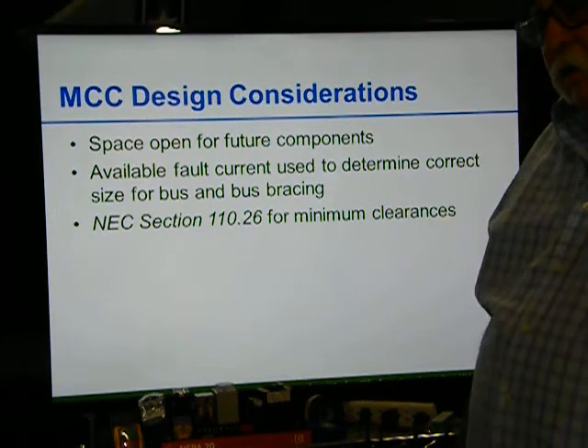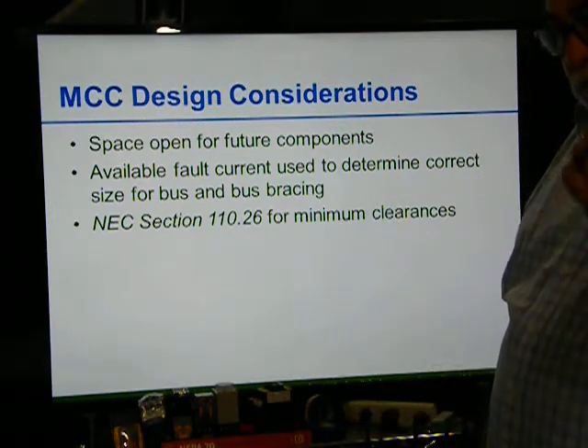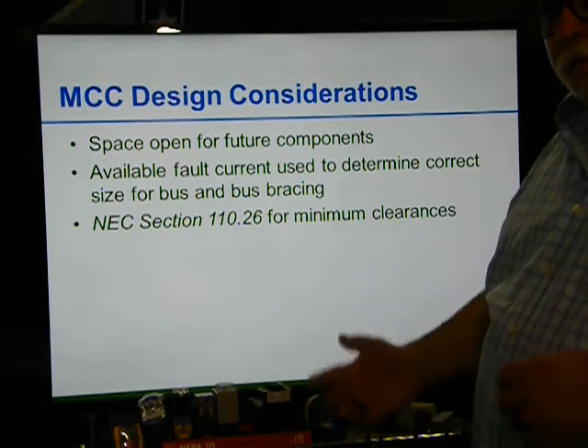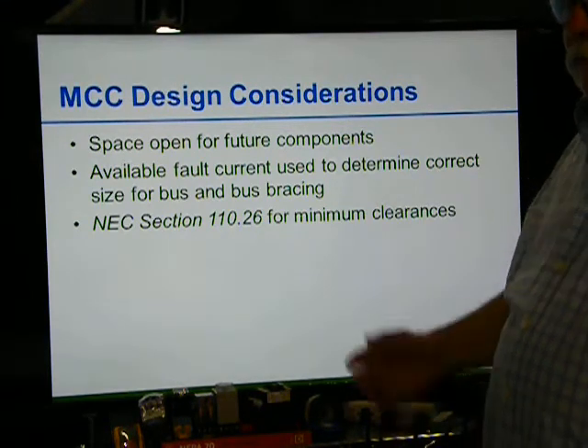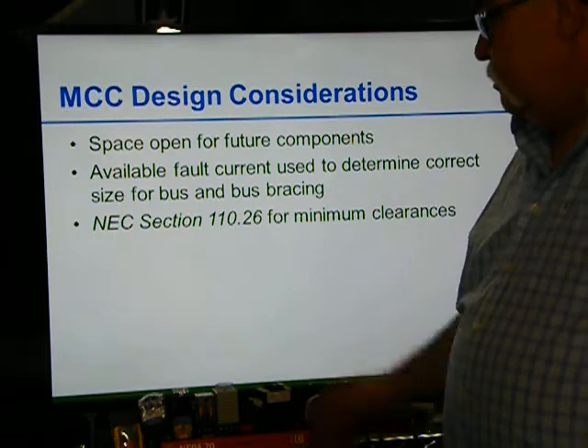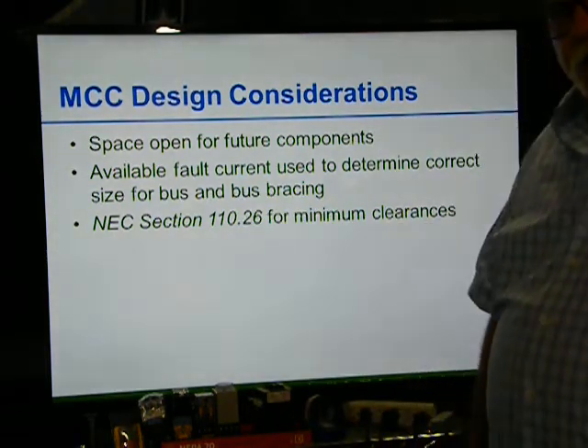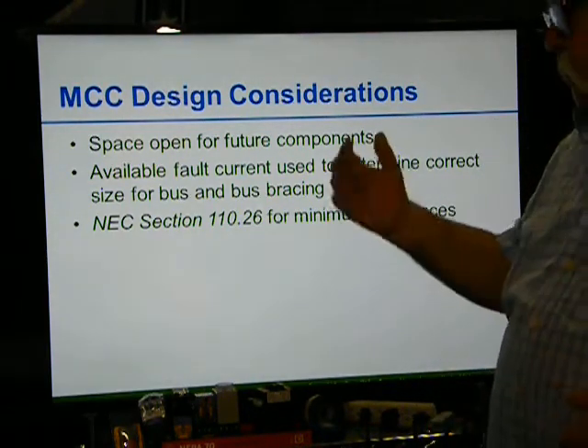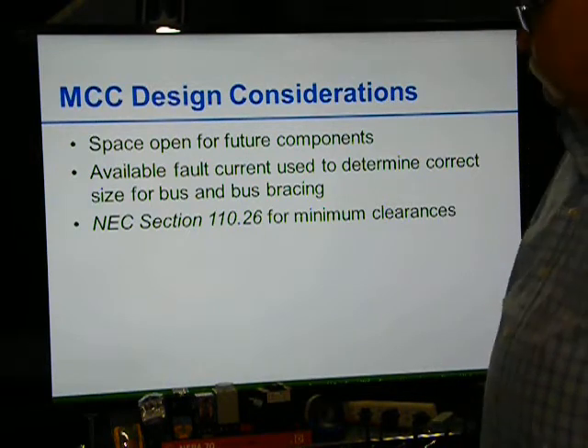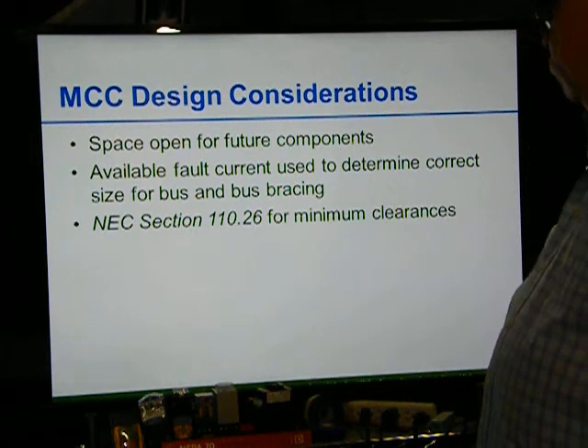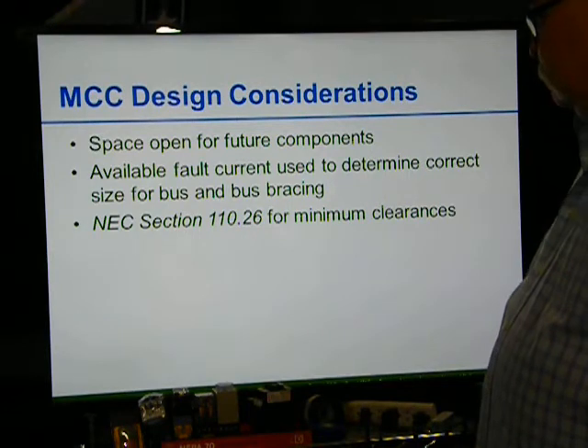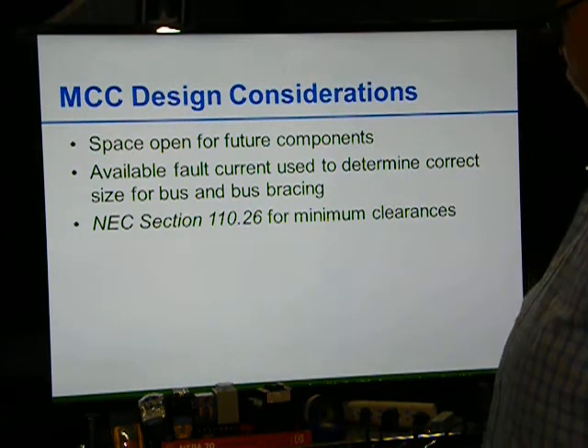What's a fault current? Well, you figure your size, your amperage. If there's a fault to ground, a ground fault, you consider resistance and current and everything else, and you size the bus to carry the fault. The last thing you want is this bus melting on a ground fault. And bus bracing. NEC Section 110.26 for minimal clearance.